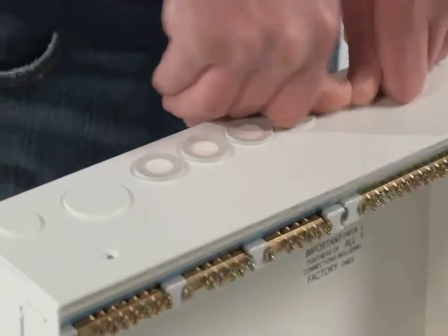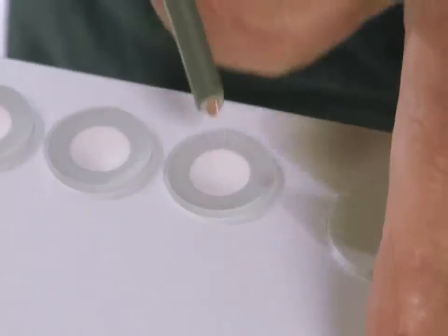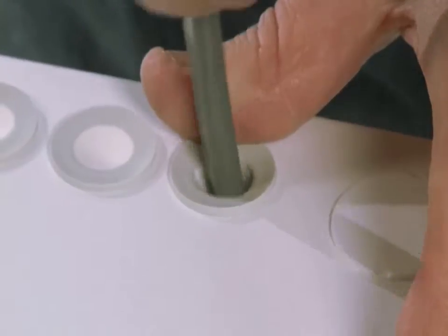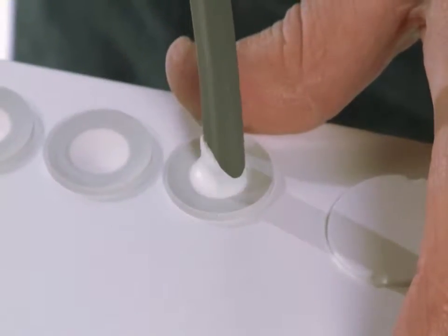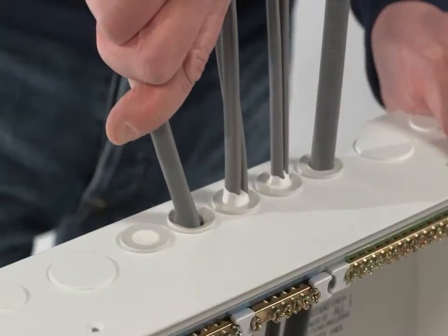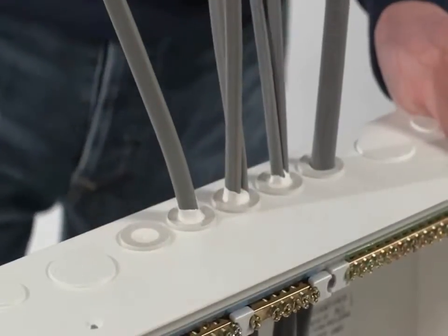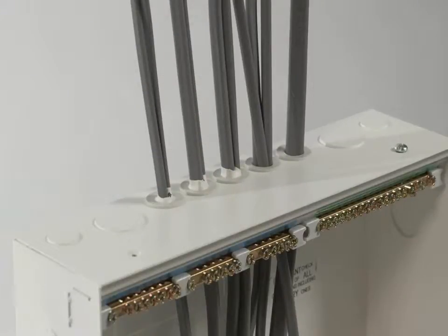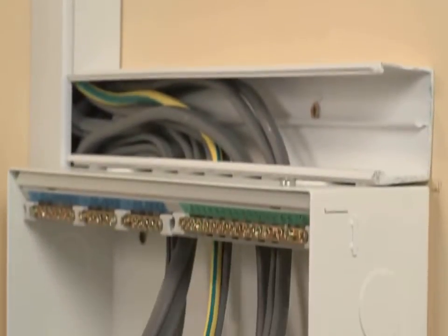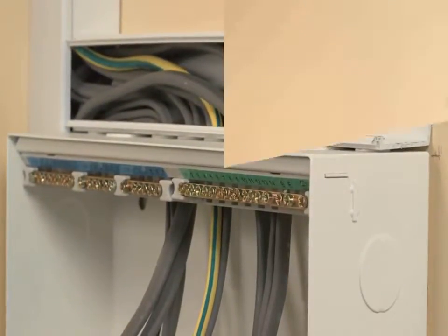Alternatively, using semi-blind grommets with trunking will again give mechanical protection to the cables at the point of entry into the consumer unit and form a barrier to assist achieving the necessary IP rating on the top elevation. These semi-blind grommets are available in fire-resistant materials and automatically size themselves to the shape of the cable penetration.